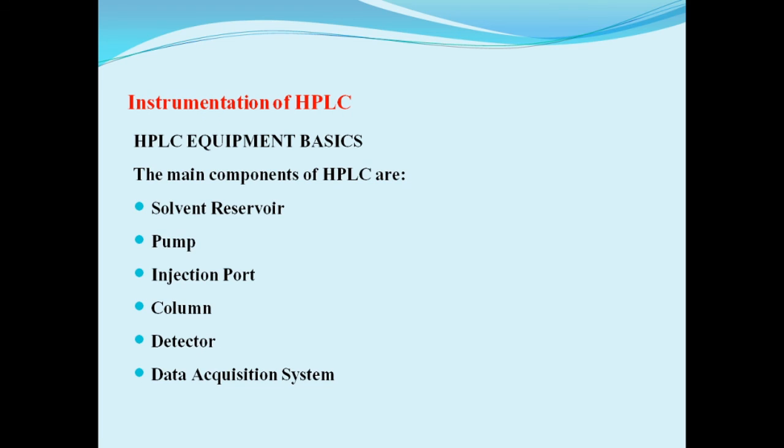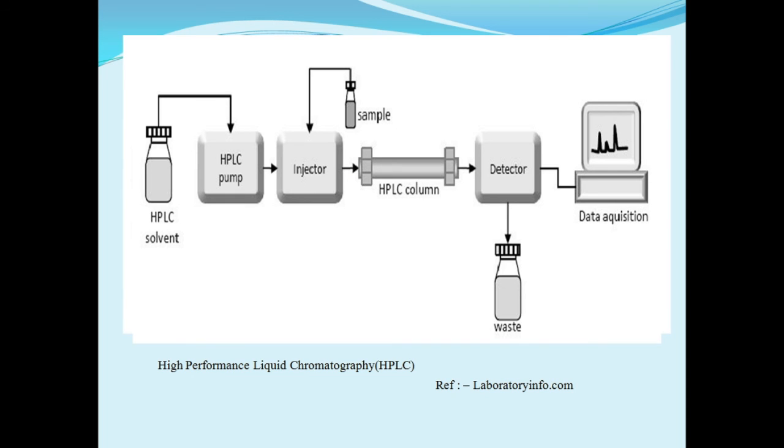Instrumentation of HPLC. The main components of HPLC are solvent reservoir, pump, injection port, column, detector, and data acquisition system. These are in the block diagram.